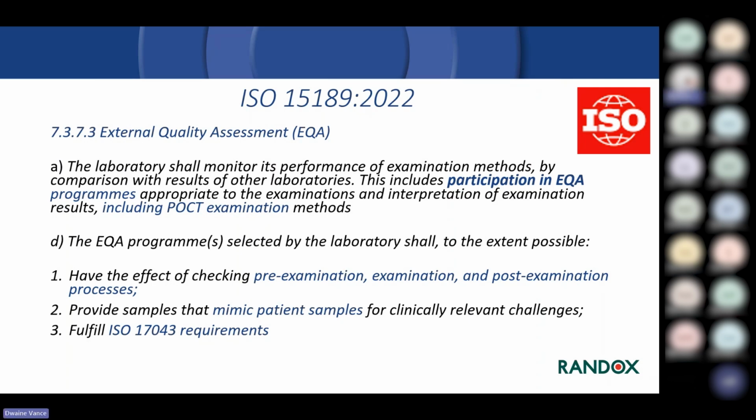So the sample must be commutable and should react to the examination system in exactly the same way as the patient sample, but also the samples provided within the challenge of the EQA should exist at clinically relevant challenges and be indicative of a clinical scenario. And the EQA provider should also fulfill ISO 17043 requirements.